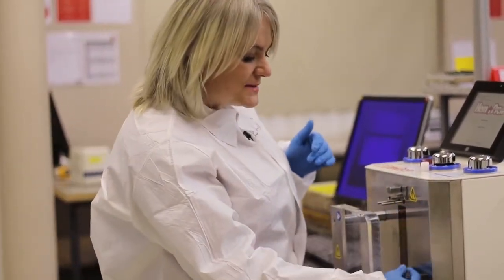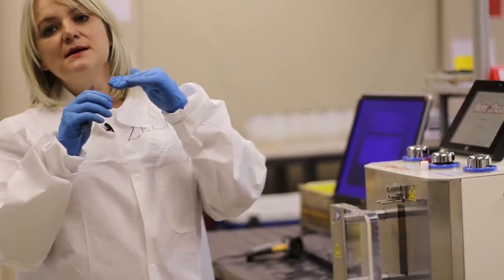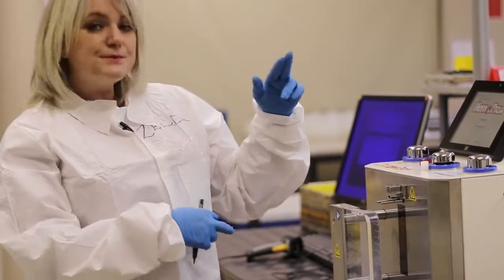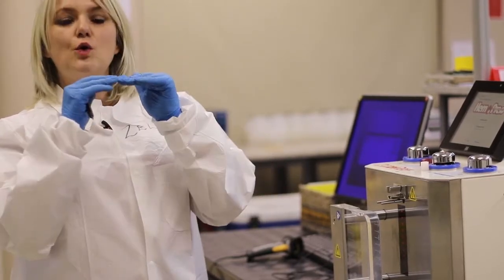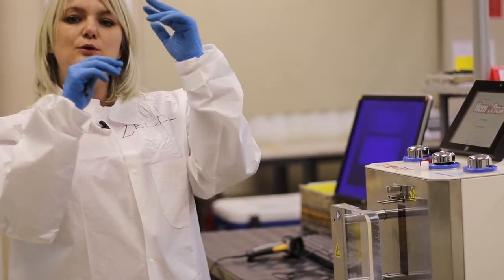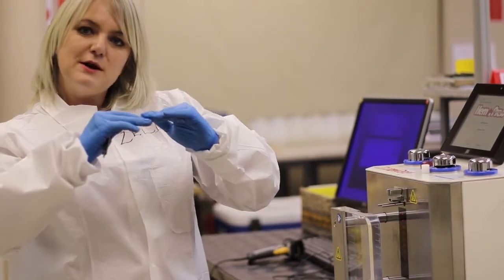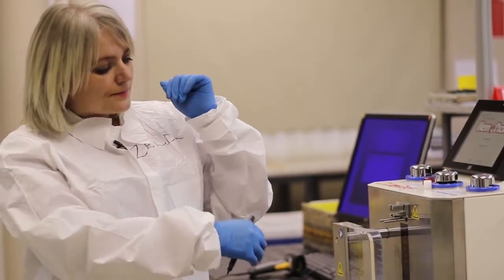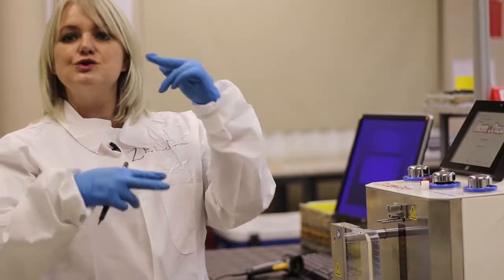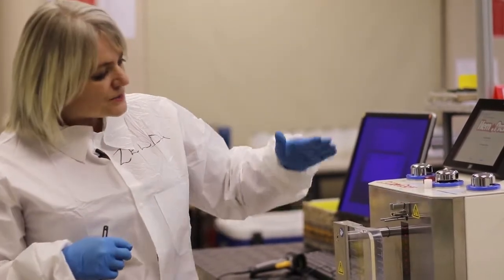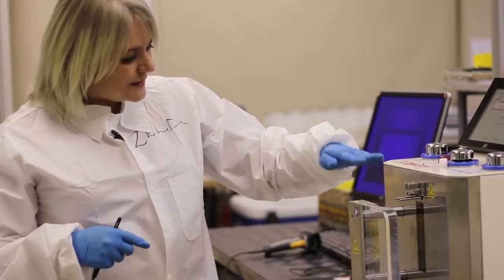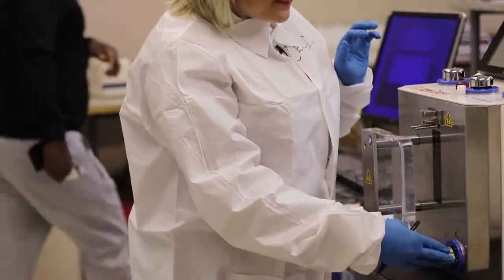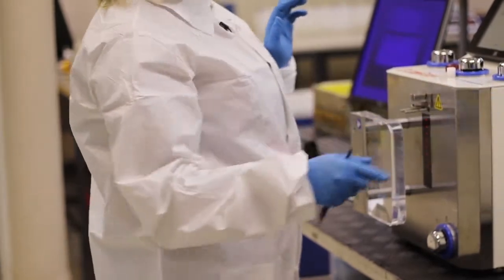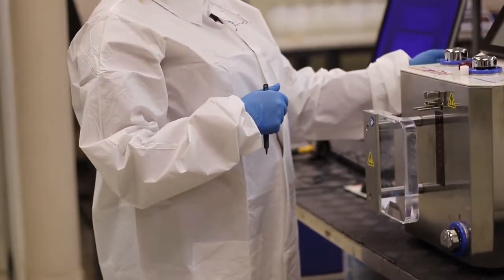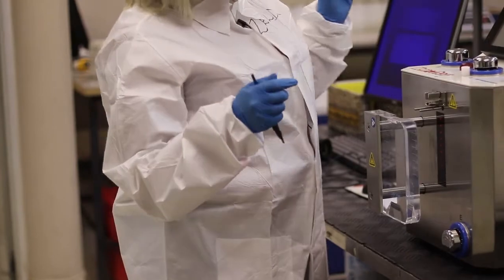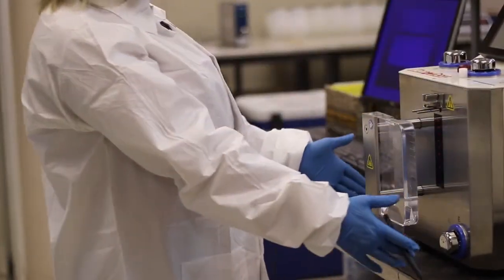Then we have our level sensors. The level sensors are what's guiding the clamps to open and close. If your red cells go above a certain line, it will close clamp A. If it drops below a certain line, it will then open and close clamp A and E based on the level sensors. That's your pressure plate. Clamp E will be for your red cells. Red cells will hang on the right, plasma to your left. That is the front side of the machine.